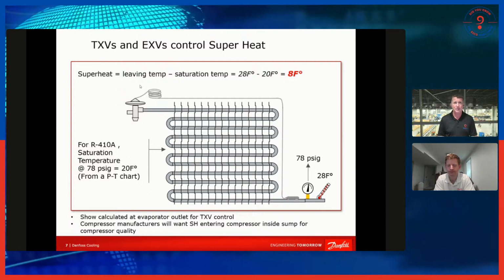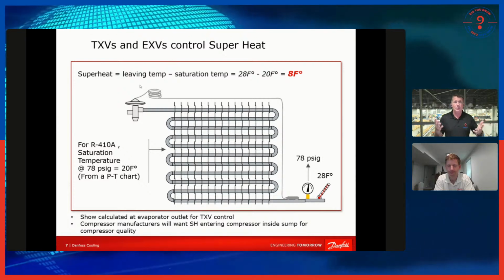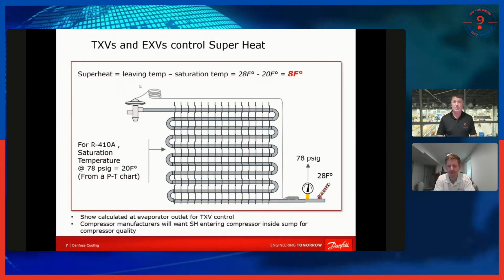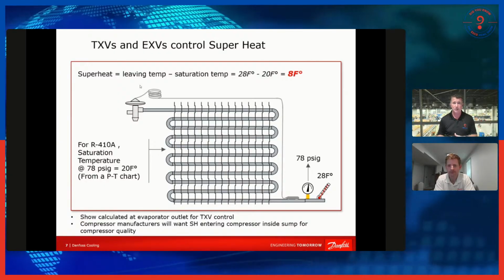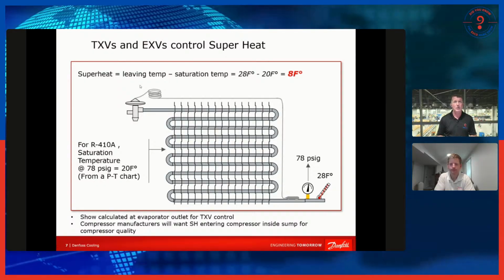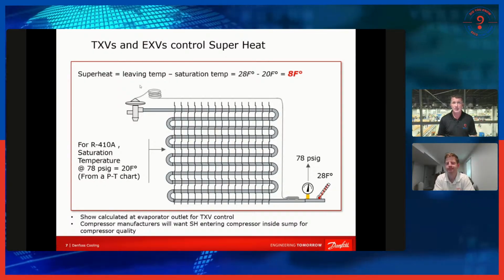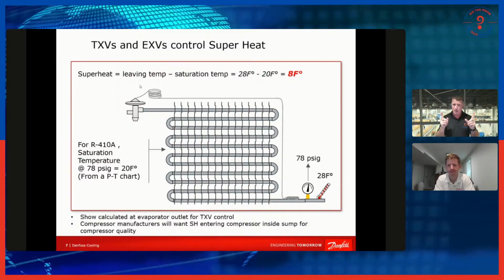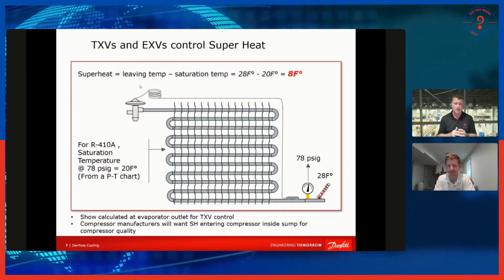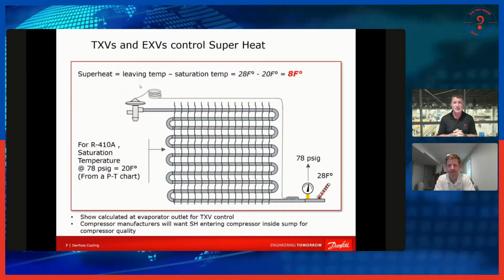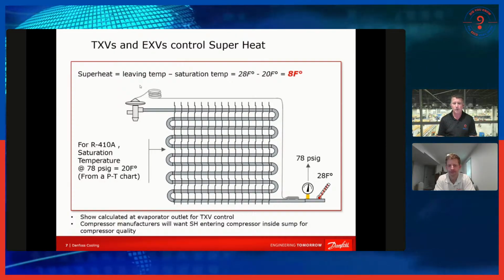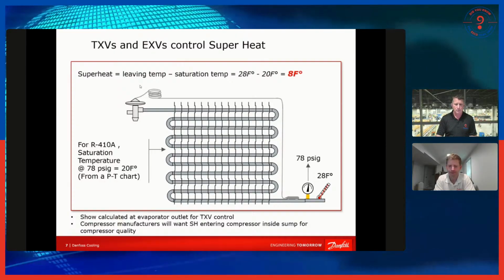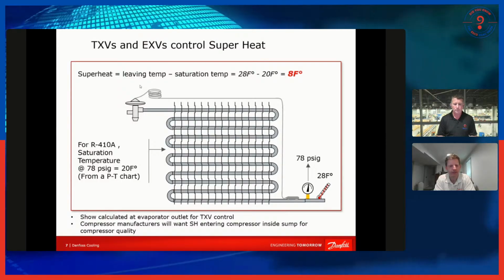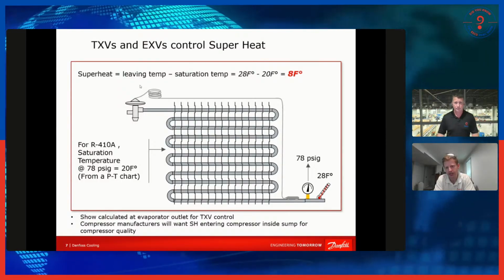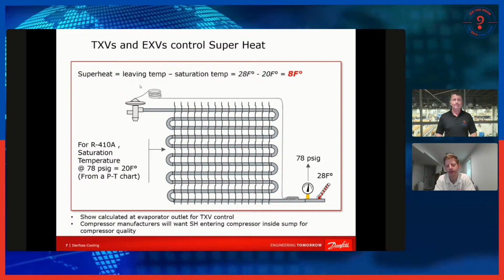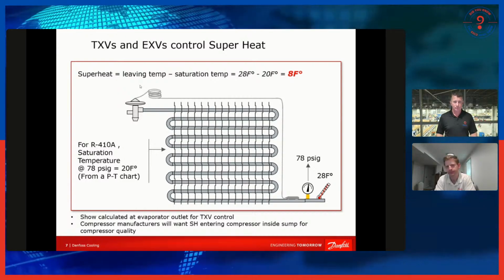So when we look at the accuracy, typically people would think, okay, we go from piston to a thermostatic expansion valve, there's a huge difference. Why would we need to go to an electronic expansion valve? Well, there's times when we go into the fixed thermostatic expansion valves that we have a really wide window of operation, a lot of float, which we wouldn't see in those electronic expansion valves when they're really finely tuned. Yeah, there definitely can be, because as the conditions change, the superheat that the TXV controls to shifts around.